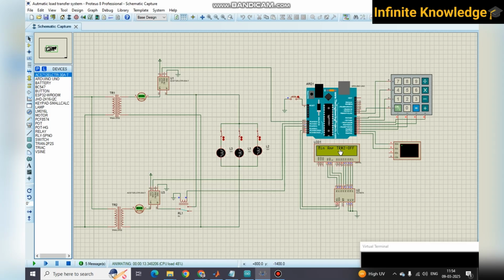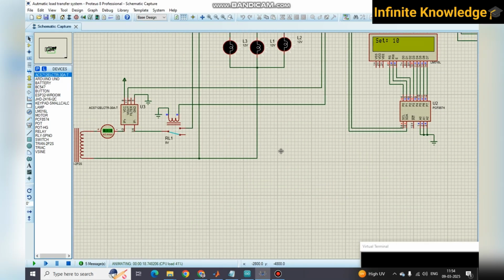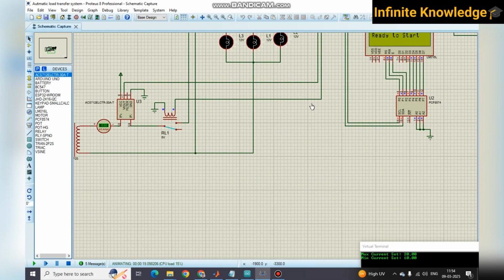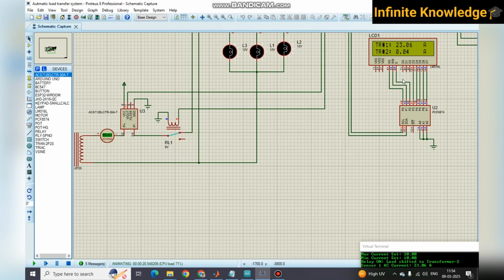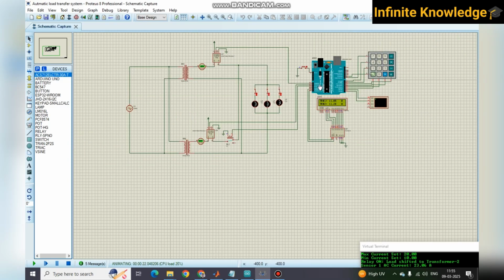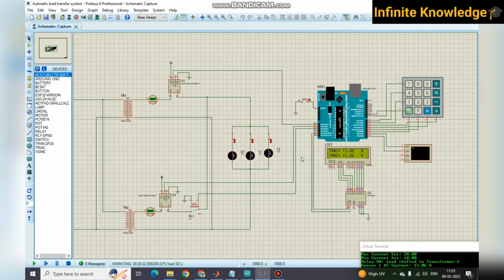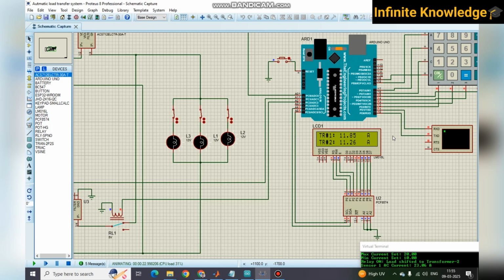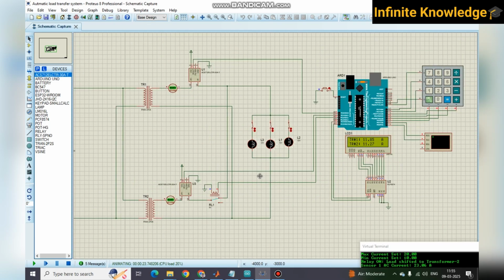Similarly, I need to add the minimum ampere as well. At what ampere do I need to isolate this breaker? Let's consider 10 ampere. If the load is less than 10 ampere, then isolate it. So I start the simulation. As I start the simulation, this breaker gets on. You can see TR1 taking 23 ampere, and at the same time this turns on, and now both transformers come into the picture and feed the load. Both transformers share the average current.